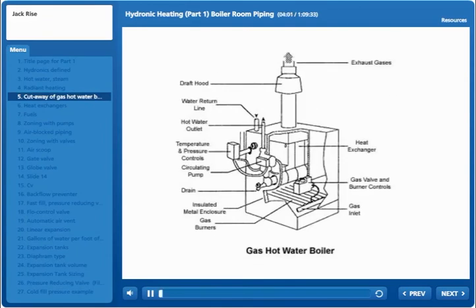Okay, what you're looking at here is a cross-sectional view, or at least a cutaway view, of the most common hot water boiler you're going to find in residential work, and that's the gas-fired hot water boiler. All right, you can see the gas burners down along the bottom with the gas controls. They're calling out an insulated metal enclosure. That's called the boiler jacket. Okay, and it's nothing but a sheet metal box that's lined with anywhere from 1/2 inch to 1 inch fiberglass, much like fiberglass lining on a duct system.